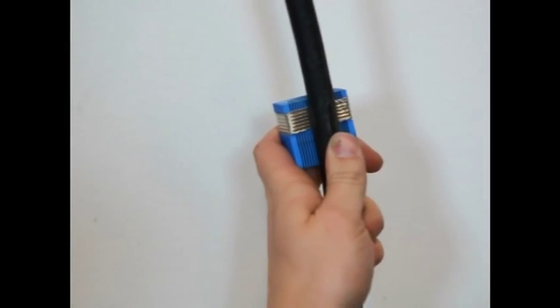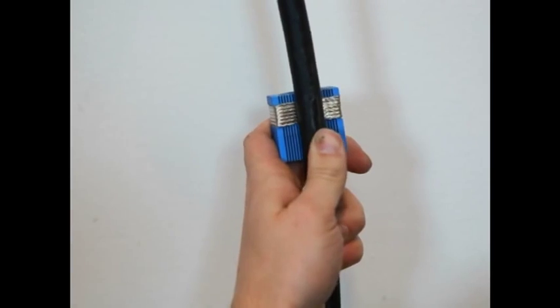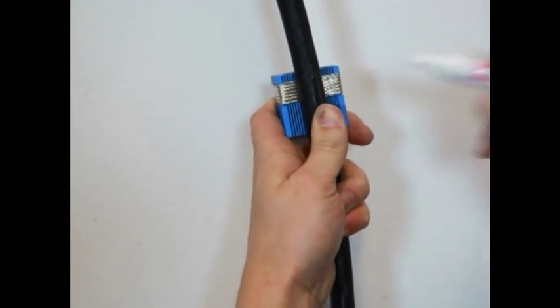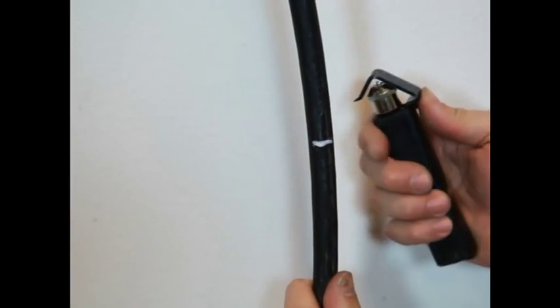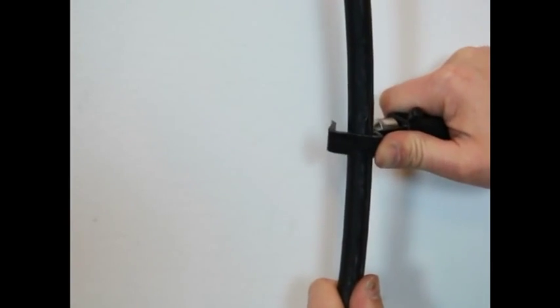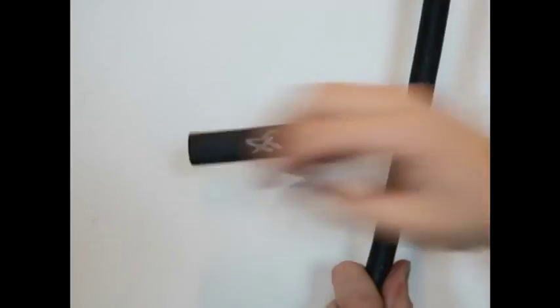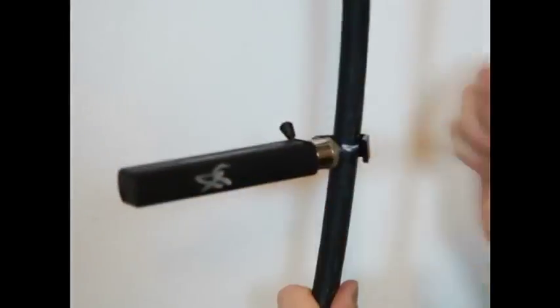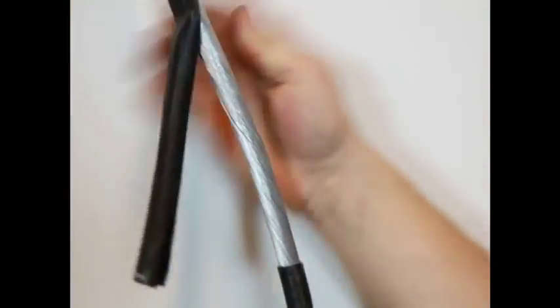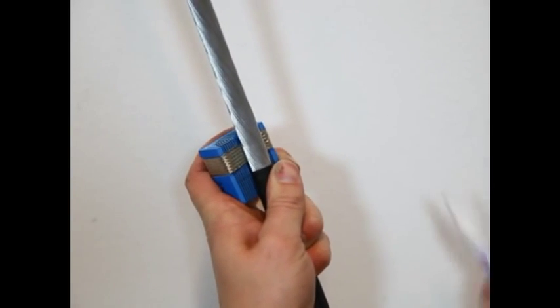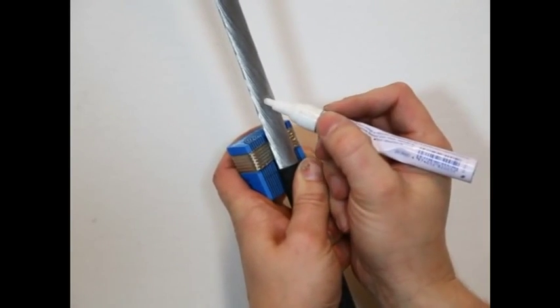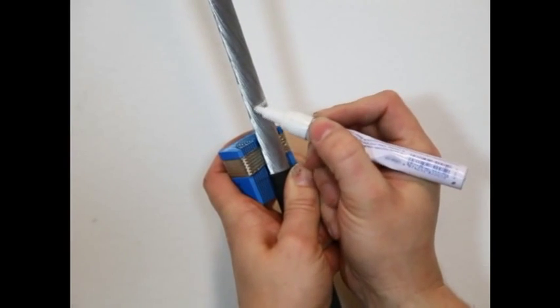If you intend to finish the armor with shrink tube, mark precisely where to cut the outer sheath and cut it accordingly. Then mark where to cut the armor. It must extend beyond the module to support the shrink tube.